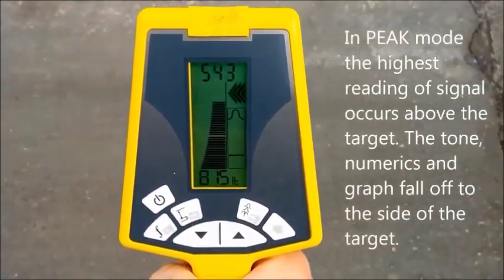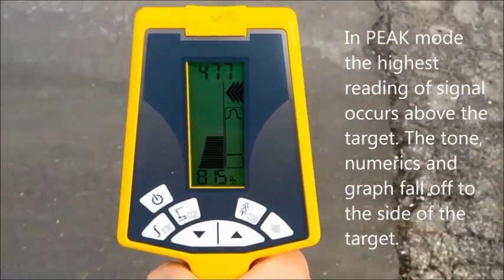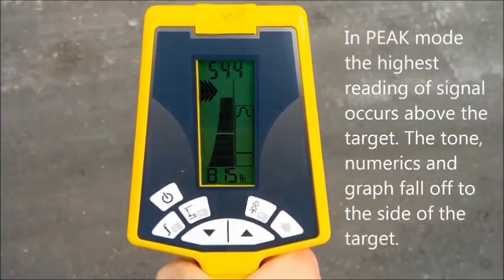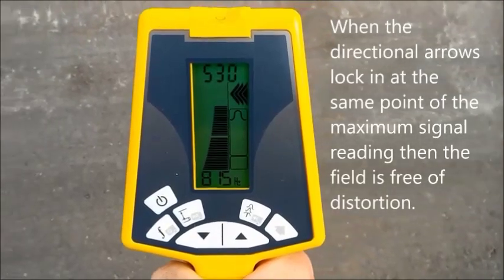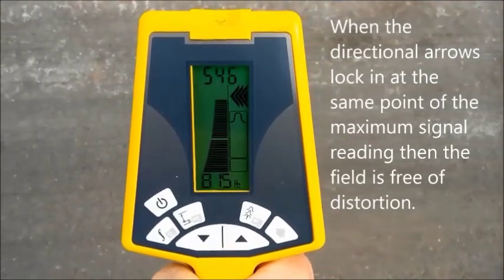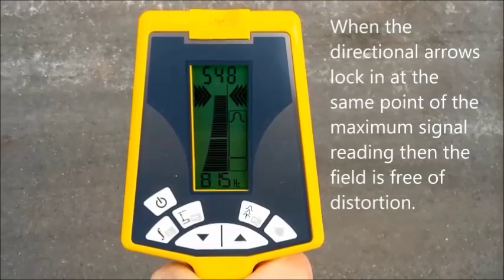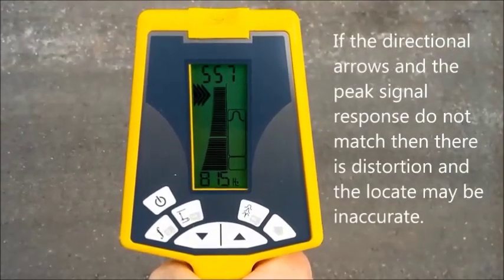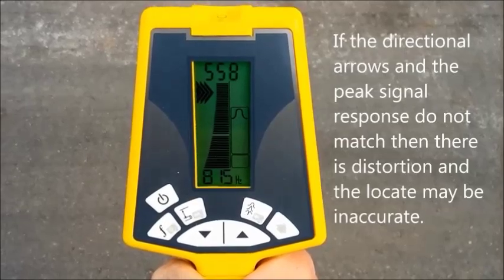In peak mode, the highest reading of signal occurs above the target. The tone, numerics, and graph fall off to the side of the target conductor. When the directional arrows lock in at the same point of the maximum signal reading, then the field is free of distortion. If the directional arrows and the peak signal response do not match, then there is distortion and the locate may be inaccurate.